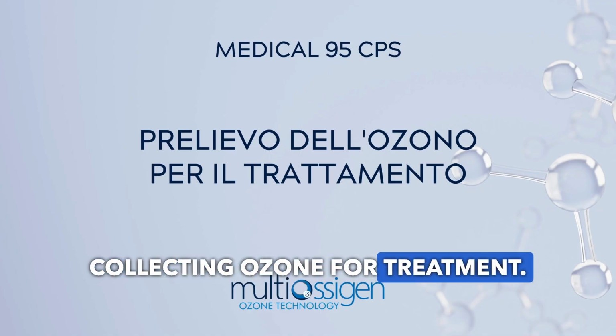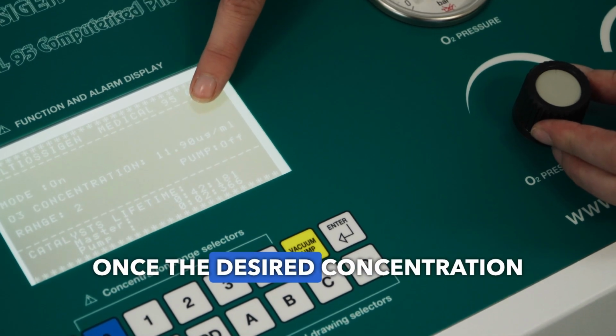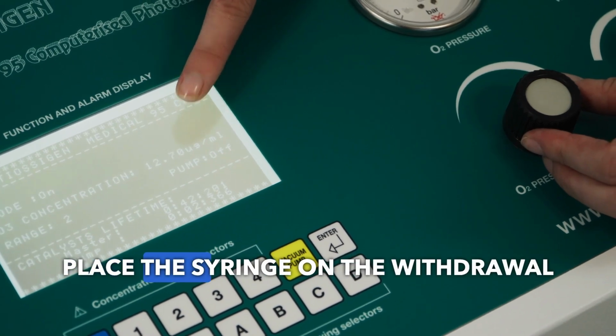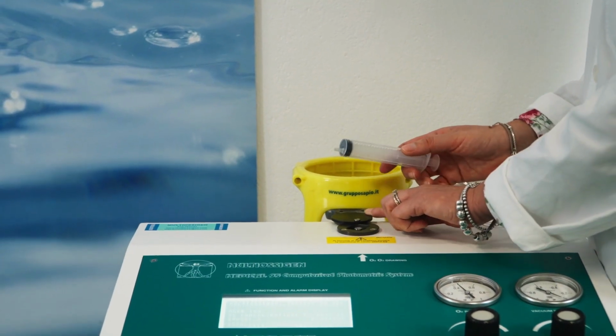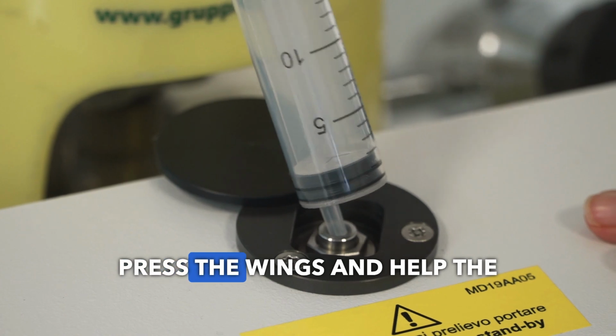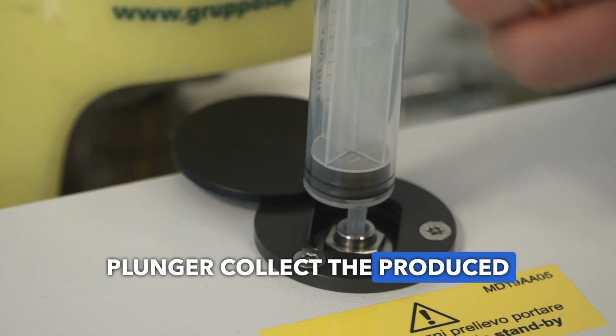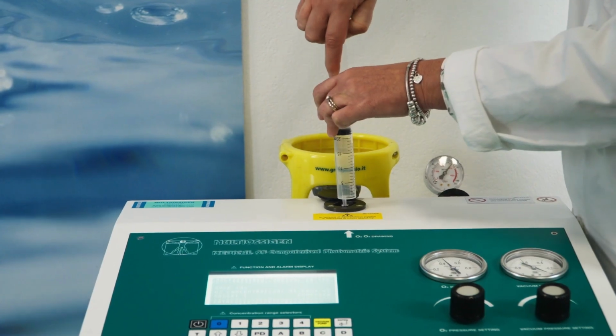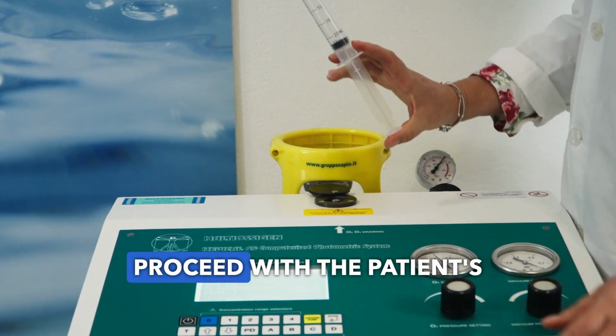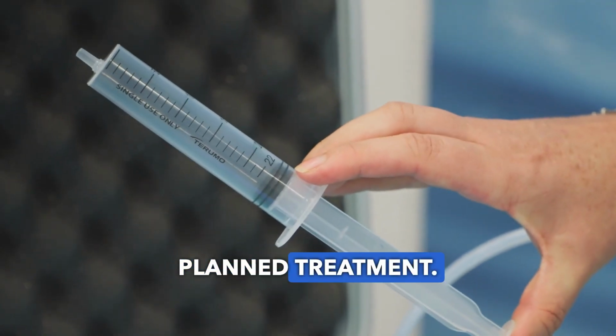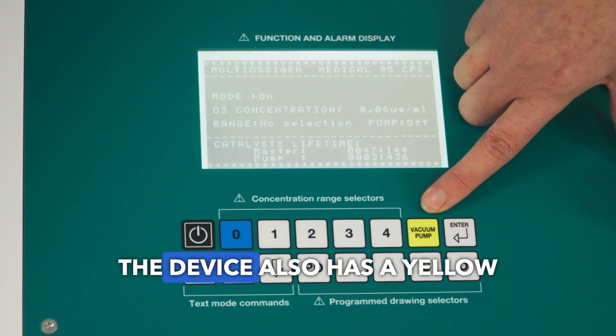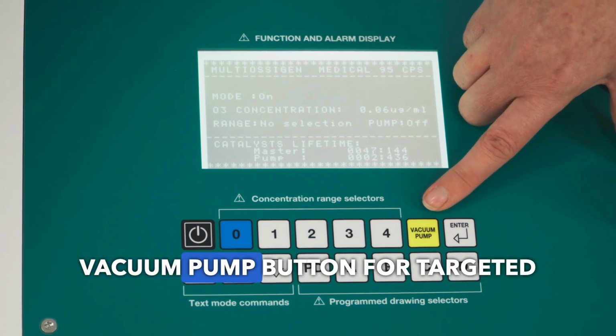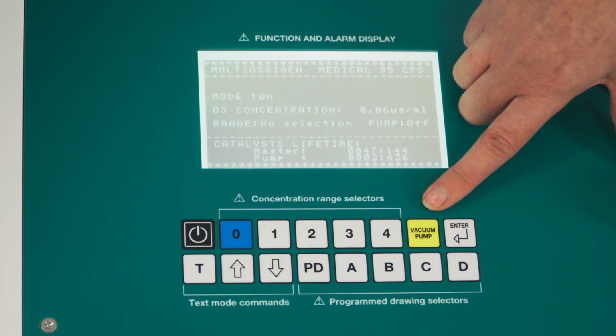Collecting ozone for treatment. Once the desired concentration is reached, place the syringe on the withdrawal valve. Press the wings and help the plunger collect the produced gas. Once the syringe is filled, proceed with the patient's planned treatment. The device also has a yellow vacuum pump button for targeted treatments.